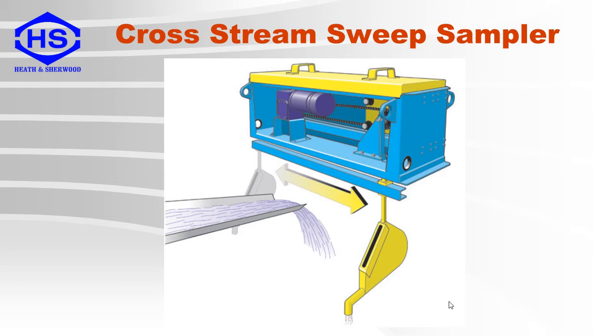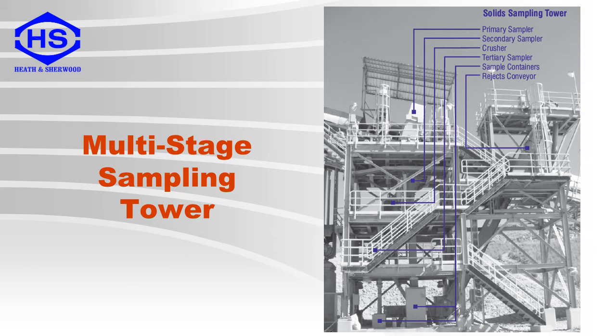Here is another example of a cross-stream sweep sampler for solids. It is an electrically driven cutter which moves across the discharge flow from a conveyor belt. This is an example of a complete composite sampling tower. Increments are taken via an arm sampler, which drop down to a secondary sampler. Increments from the secondary sampler go through a crusher for particle size reduction, before going to a tertiary sampler, and then on to sample containers. The rejects go to a high-inclination conveyor belt and are put back on the process belt.